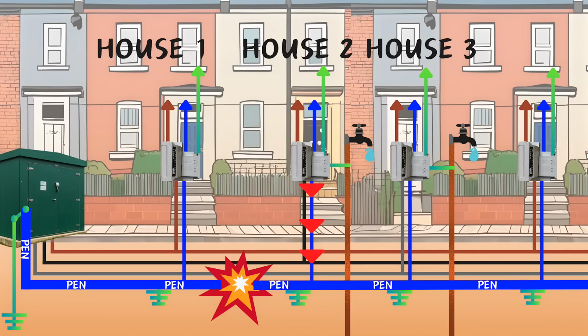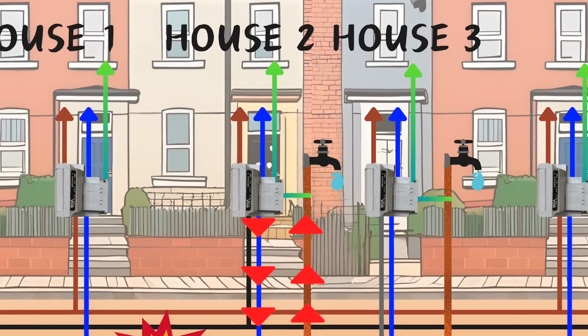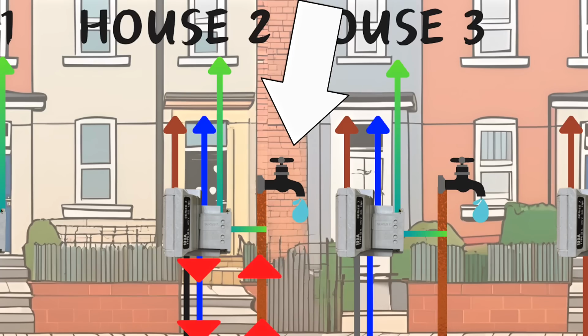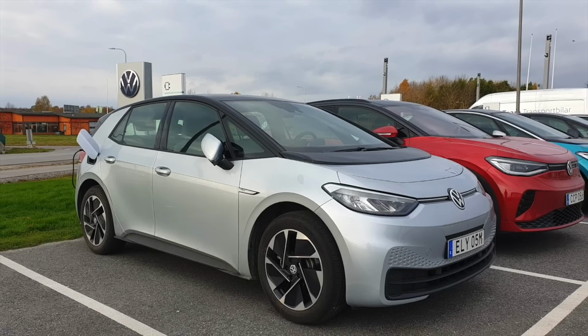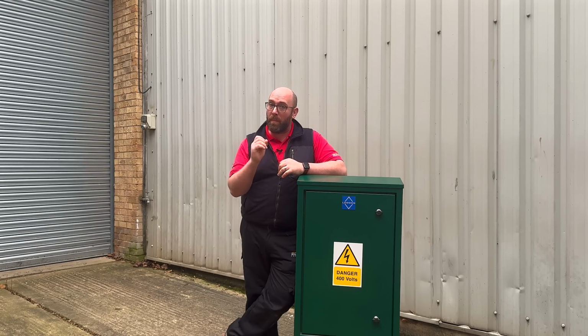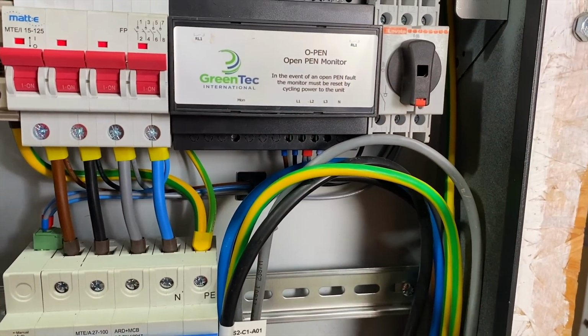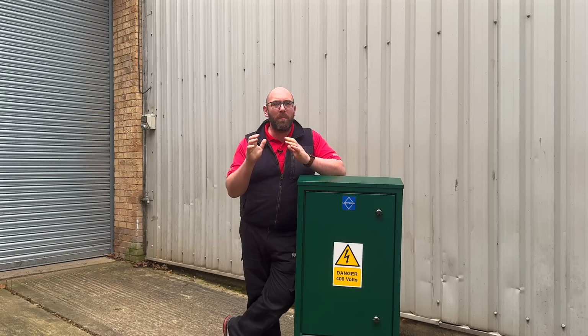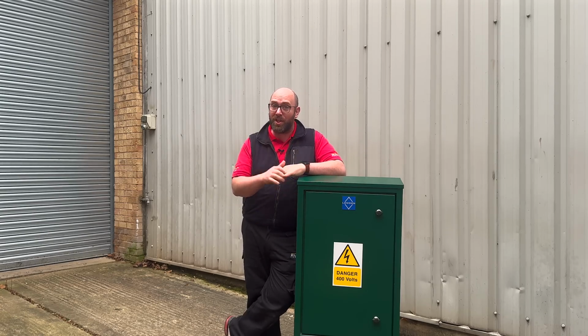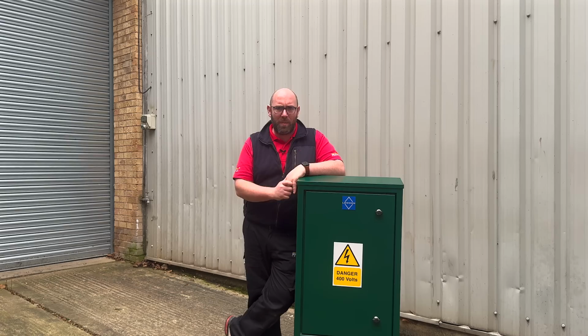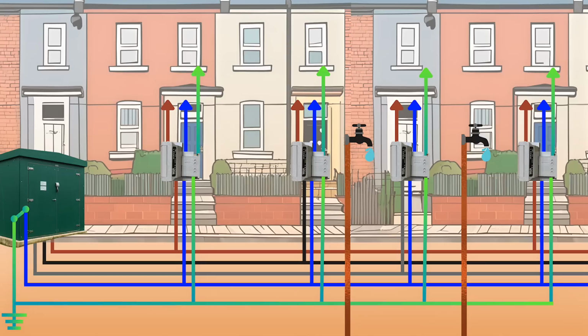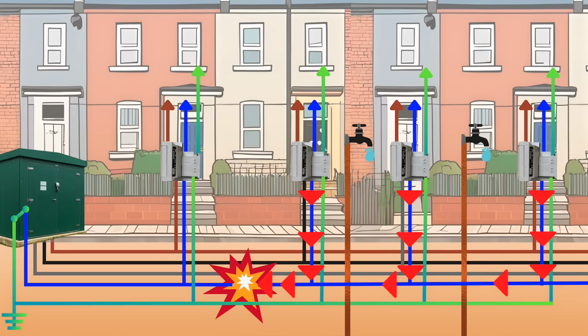As current is flowing through the line, it returns via the neutral, or at least it would if the neutral was there. This means that a potentially dangerous potential could rise in any metalwork that is connected to the MET, which could include an electric car. This dangerous rise in potential could be discharged through a person if they were stood on the literal earth, as a difference exists. This is why PEN fault protection is really important in car chargers. But this problem only exists with a TNCS due to the combined nature of the earth and neutral, but not in the TNS system, which brings us back to our question: do we need to fit PEN protection on a TNS? We can see here that if an open circuit on the neutral was to occur, then everything in the installation would stop working, as the neutral and earth are separate.